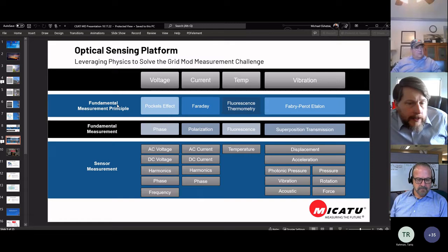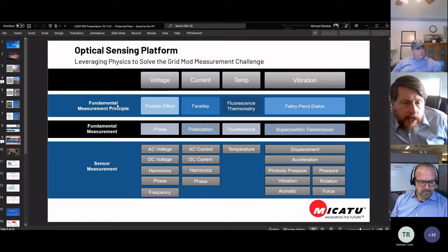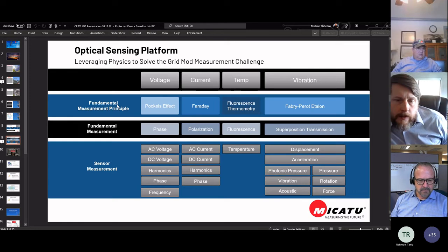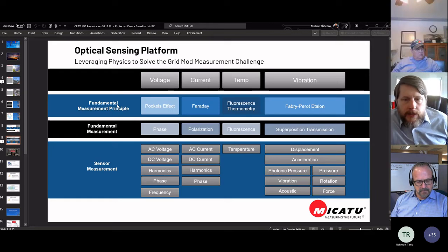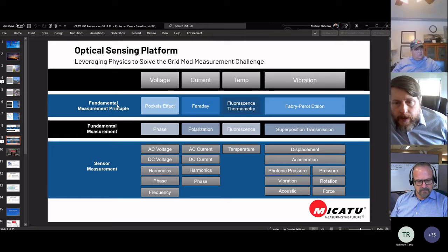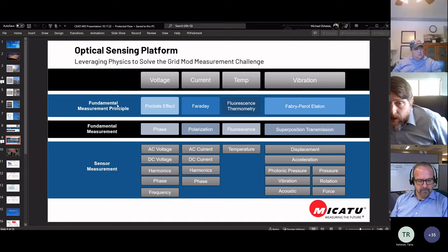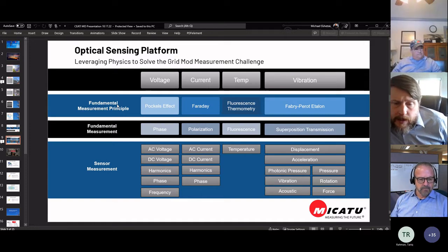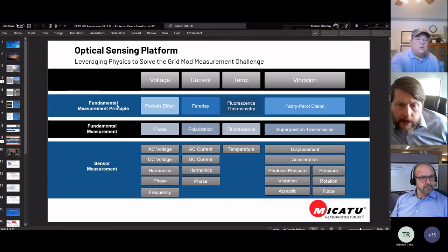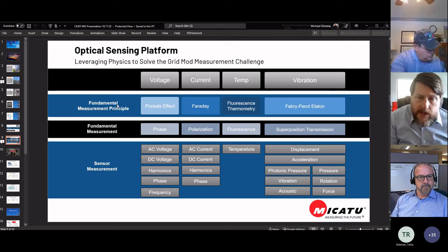Likewise, on the current side, we use something called Faraday rotation. While this isn't new to the industry—there have been many providers of optical current sensors—what really makes us different is that we're not fiber optic based. What does that mean? It means it's much easier to deploy and install than typical fiber-based systems, where you can't break the fiber. We use something called polarization to measure our current, which can measure AC current, DC current, and harmonic phase. Between the voltage and current, we can provide kVAR, all the power measurements, and the phase-to-phase, phase-to-neutral measurements across it.